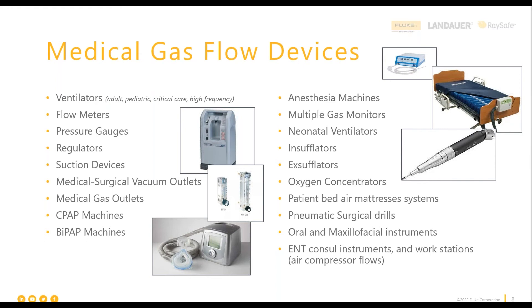Such devices could deal exclusively with pressure — take an insufflator. Maybe you're just testing flow on a wall regulator. Others might be for home use; a CPAP is a good example of that. Think about the parts of medical devices that might need testing as well. Anesthesia machines need the vent and the vaporizer tested. Also consider less obvious applications like pneumatic drills and patient bed mattresses — these all require routine maintenance and deal with medical gas flow. There's more than just vents.